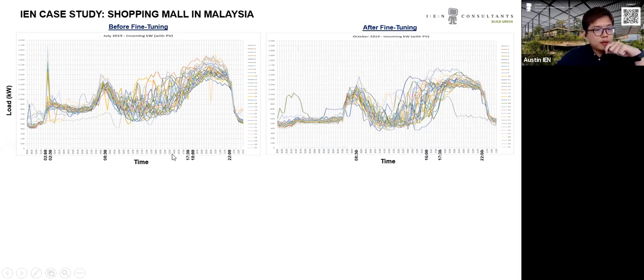On the left-hand side is the graph with data we collected before fine-tuning, and on the right-hand side is the graph we collected after fine-tuning. We noticed there was an unusual spike at 2 a.m. to 2:30 a.m., reaching until 2,100 kilowatt. After checking, it was actually because all the sets were turned on together during stock checking or stock replenishment. This was quite unusual for this mall.